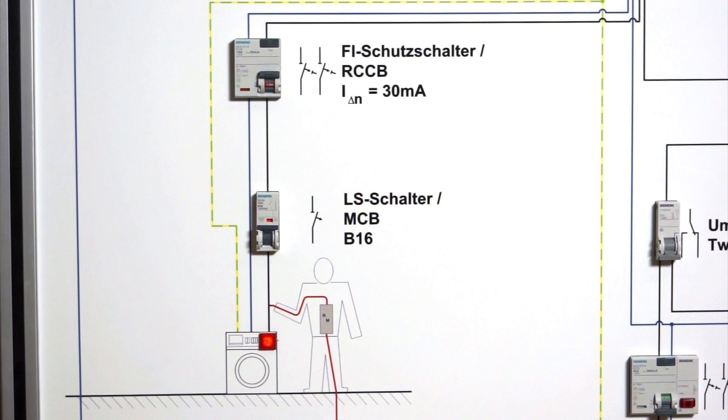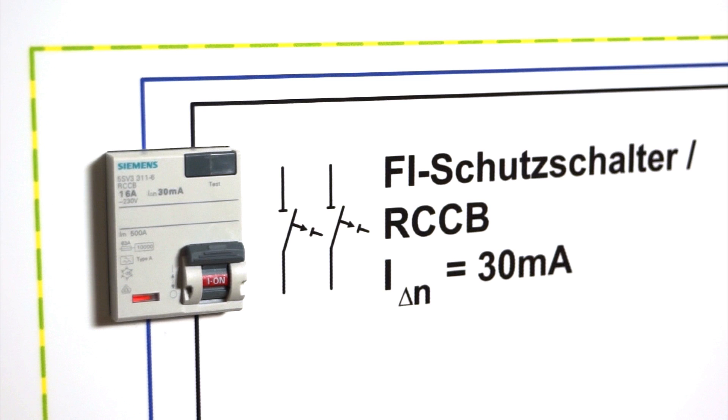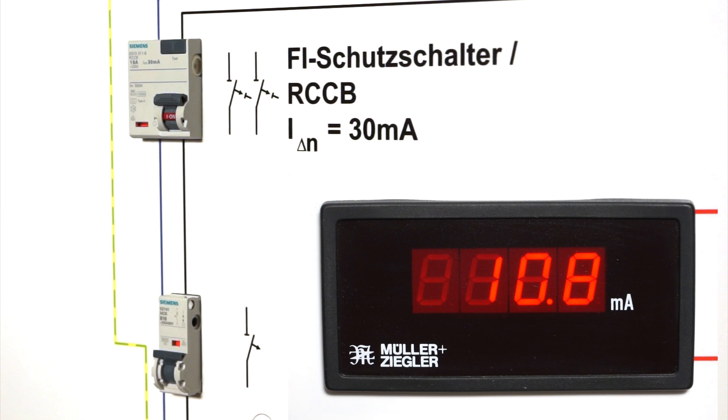What you can see is a fault current generated by somebody coming into direct contact with a live component. Such currents pose a risk to personal safety from as little as 30 milliampere. The tripping range of the RCCB is between 15 and 30 milliampere.